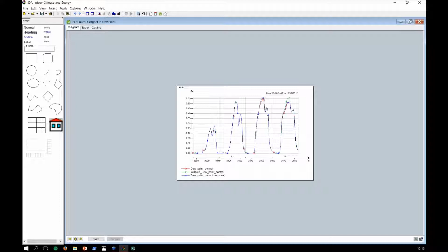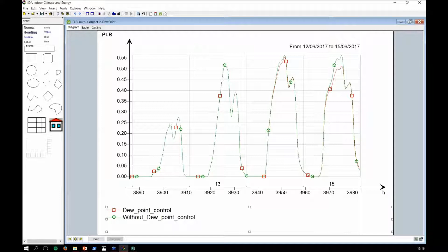Something interesting to see here is the PLR. I'm going to again zoom in, and you're going to see that having realistic coefficients on your performance curve, your chiller rarely operates at full load. Here it's operating at 55% in the worst case on June 15th. Actually, I think less than 1% will operate at full load, and all the rest is below. So that explains the power consumption saving.